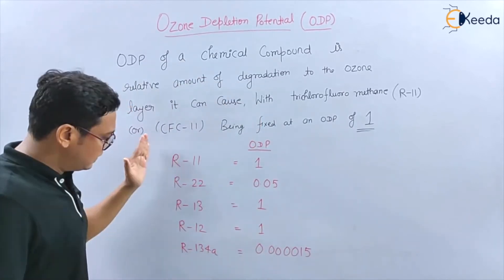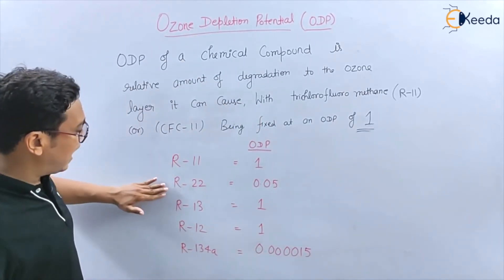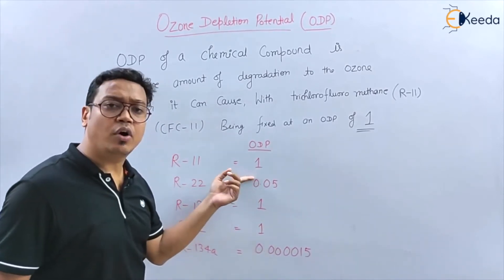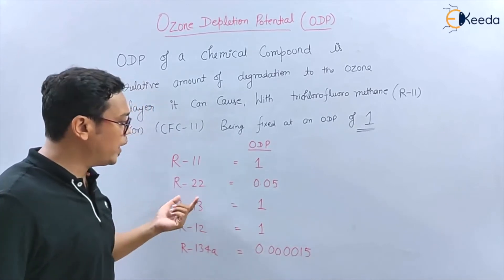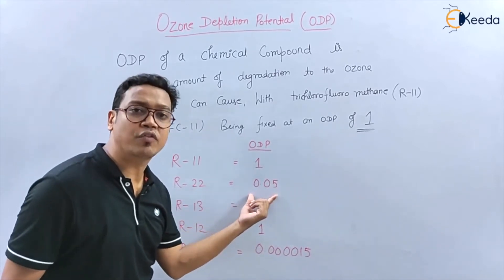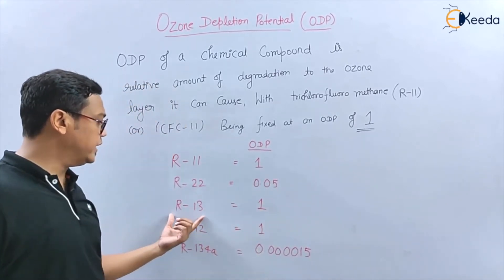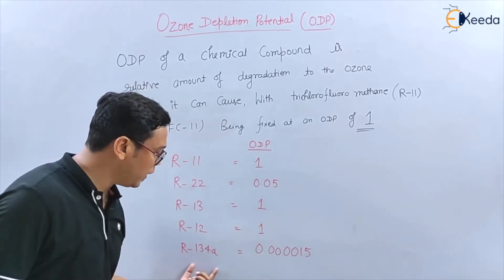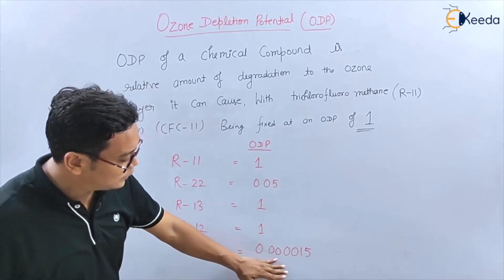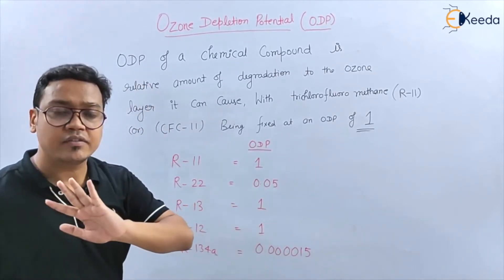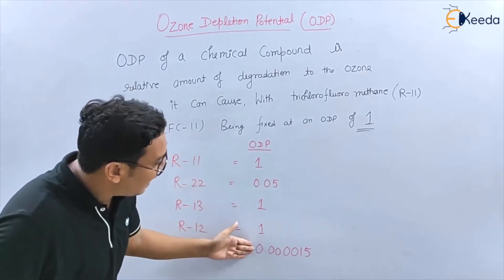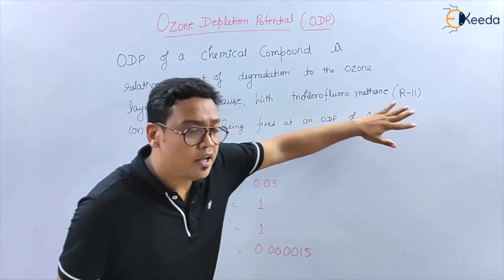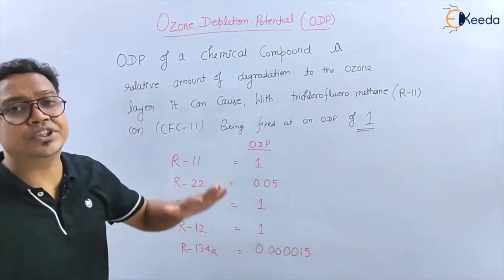Now, here are some examples: R11 has an ODP of 1, R22 has an ODP of 0.05, R12 has an ODP of 1, and R134a has an ODP of 0.000015. These potentials are all relative to R11. So this is the Ozone Depletion Potential.